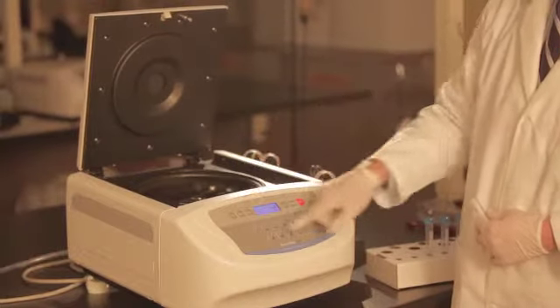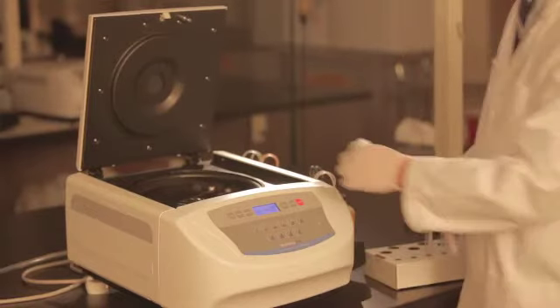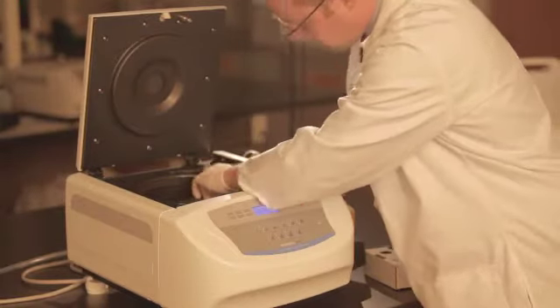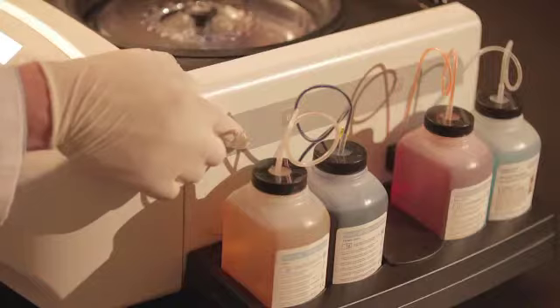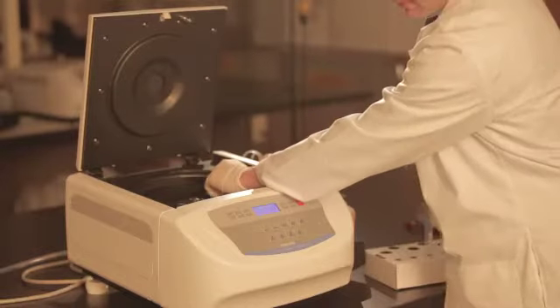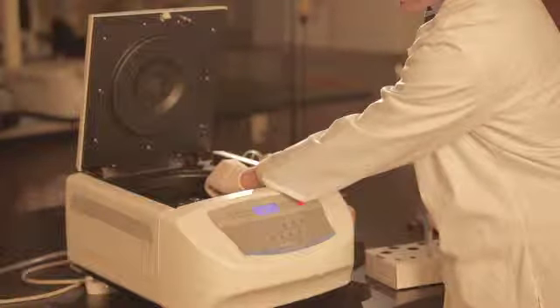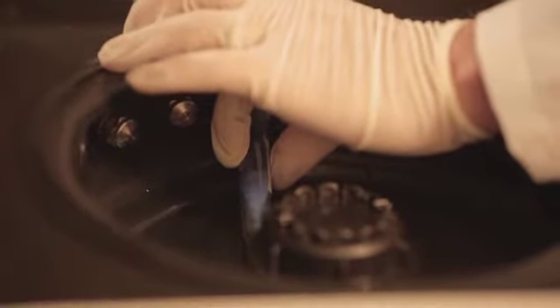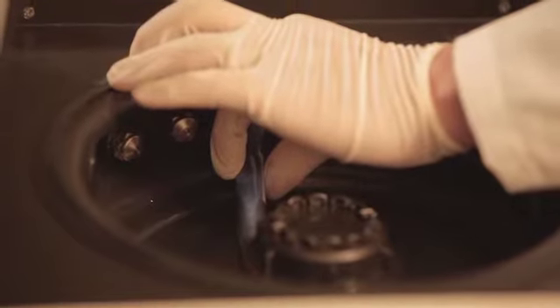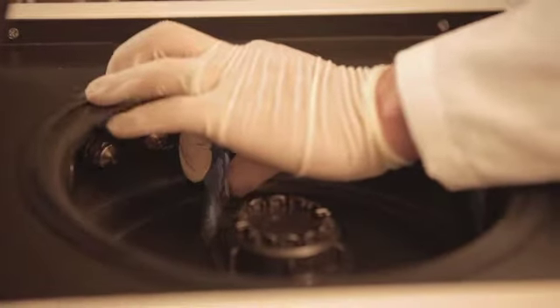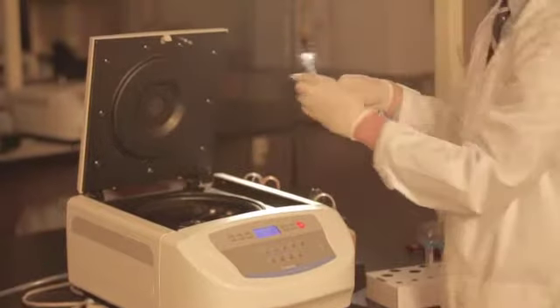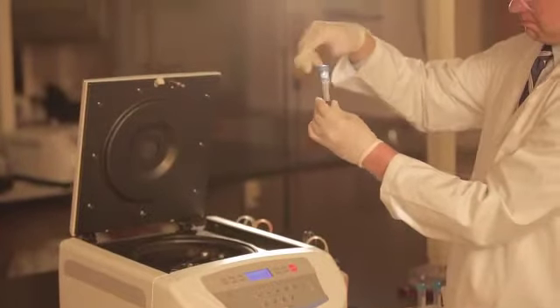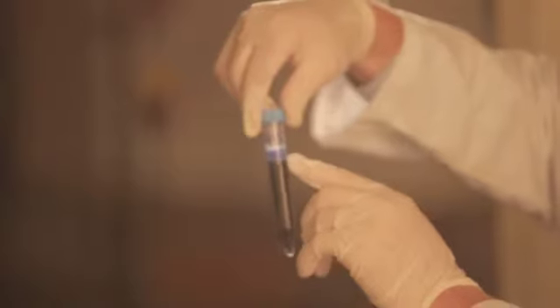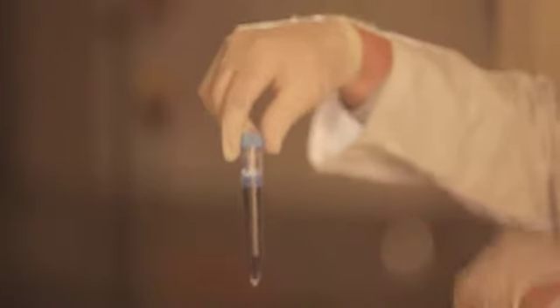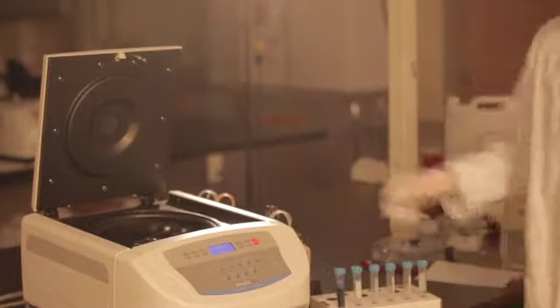Checking the spray volumes is done by exiting out of the pattern test screen, again pressing Maint and then Option 2 for volume test. The display indicates to press any prime button for a volume test. Hold one of the 15mL centrifuge tubes supplied in the nozzle maintenance kit against the nozzle being tested. The reagent will spray from the nozzle for 20 seconds. Collect the spray for the entire 20 seconds. Place the tube in the rack provided, and then compare the volume from each nozzle to the PM chart and also to the value from the previous week.